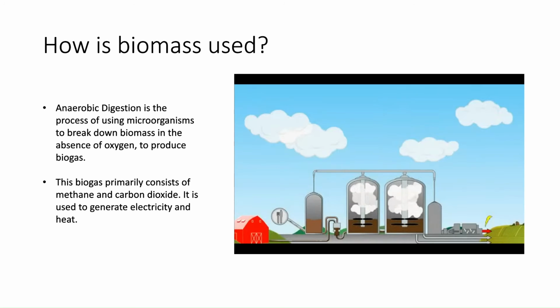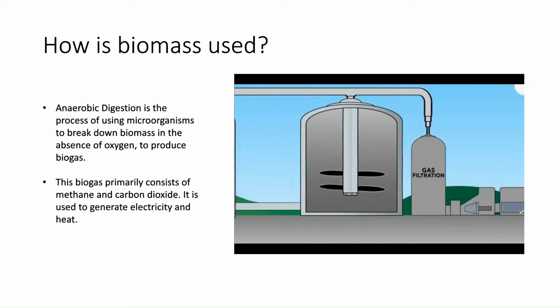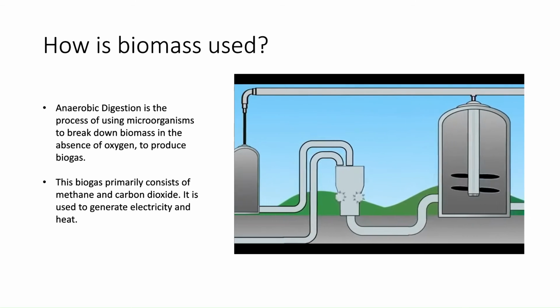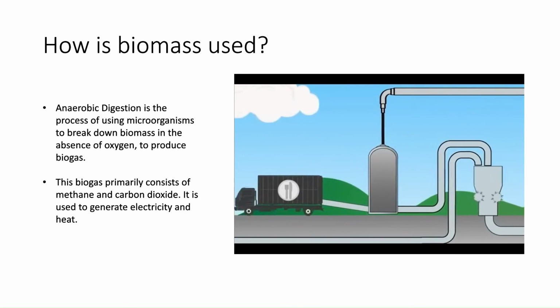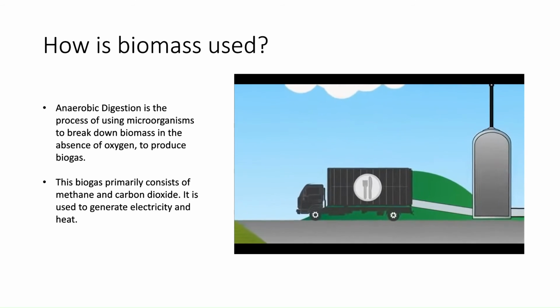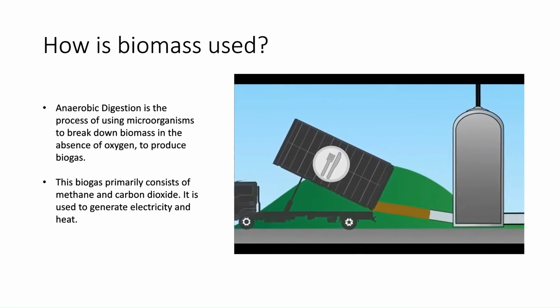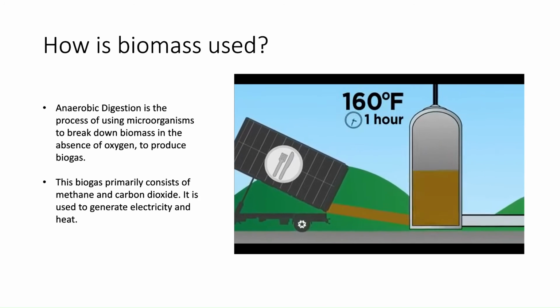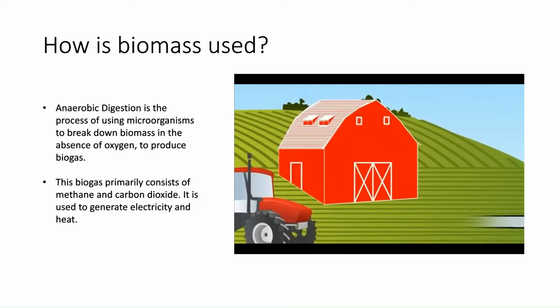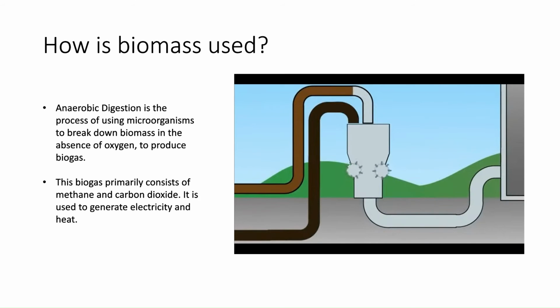The South Campus Anaerobic Digester at Michigan State University aims to reduce odor and emissions from manure, food waste, and biosolids, create a closed cycle for recycling organic material, and generate renewable energy. The digester will use a mix of dairy manure, dining hall food waste, biosolids, which are nutrient-rich organic materials, and other organic material from campus and the greater Lansing area. Once delivered, the food waste and biosolids will be heated at 160 degrees Fahrenheit for 1 hour to eliminate any potential pathogens. The material will then be mixed with manure from the MSU Dairy Teaching and Research Center and pumped into the digester.